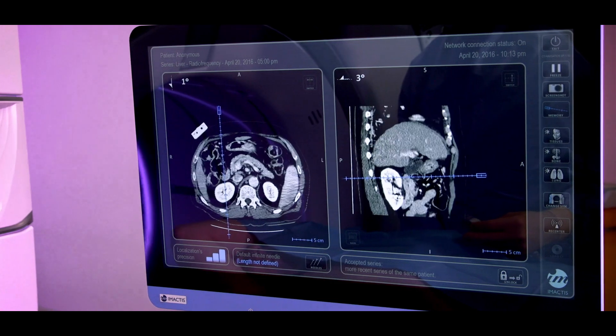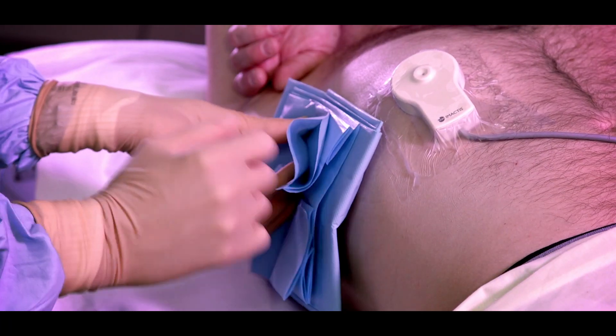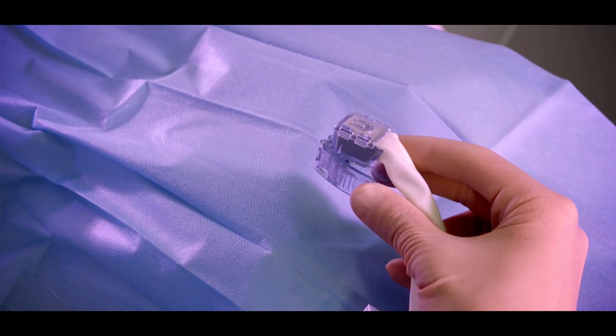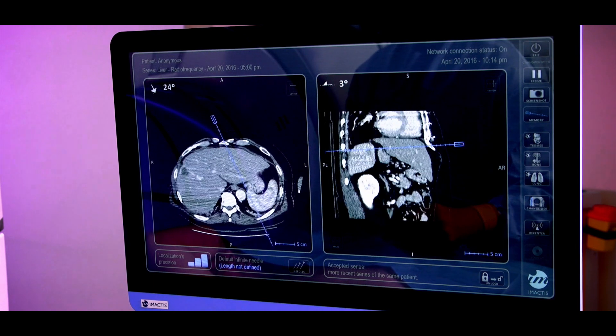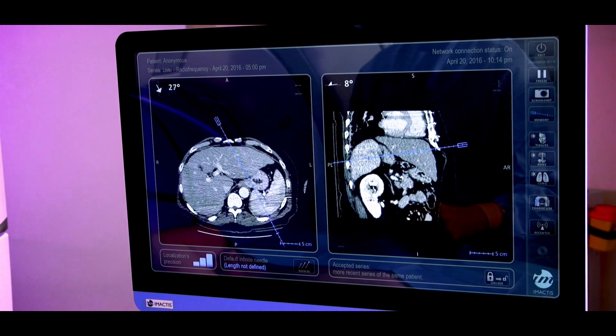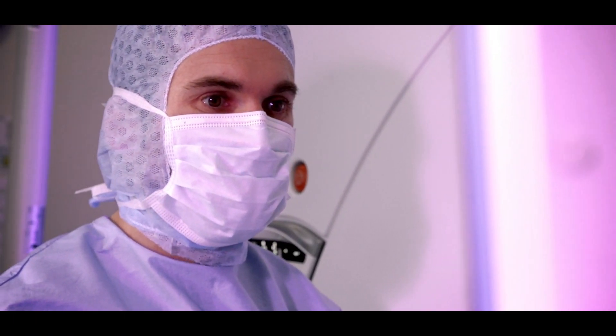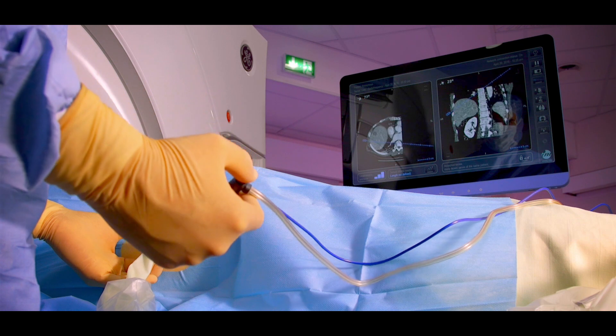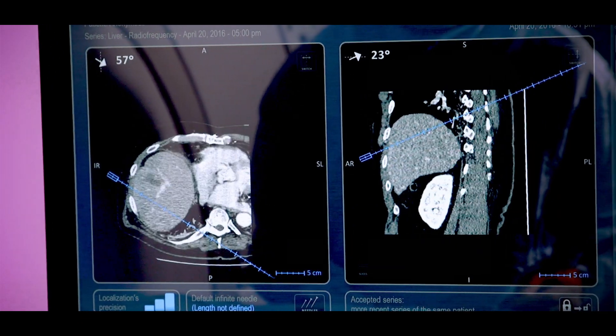The iMactis station comprises a touch screen and electromagnetic localiser with a patient fiducial and a sensor designed to be used with a needle holder. What is displayed in blue is the anticipated needle trajectory when the needle goes through the iMactis needle holder axis. The system dynamically displays the two reconstructed slices containing the needle, regardless of its orientation and with no angulation limit.